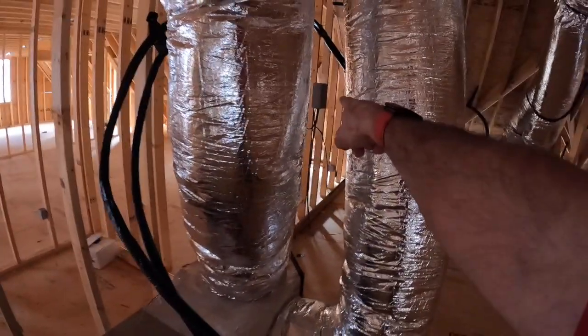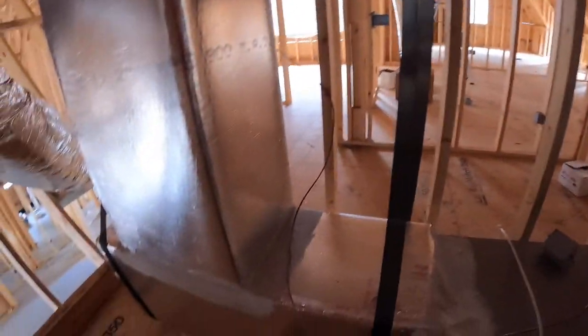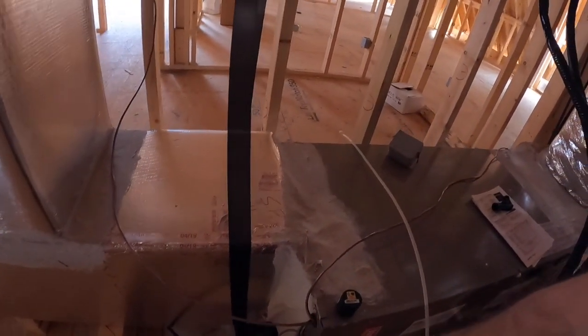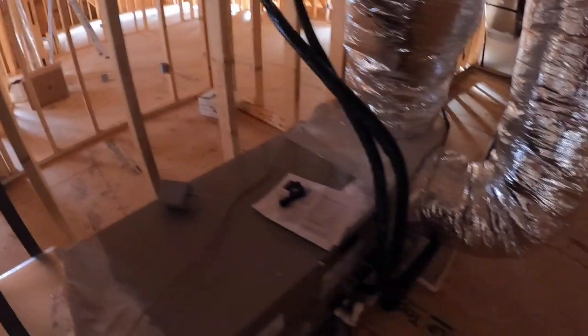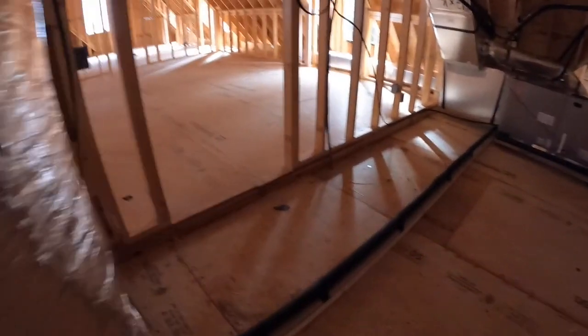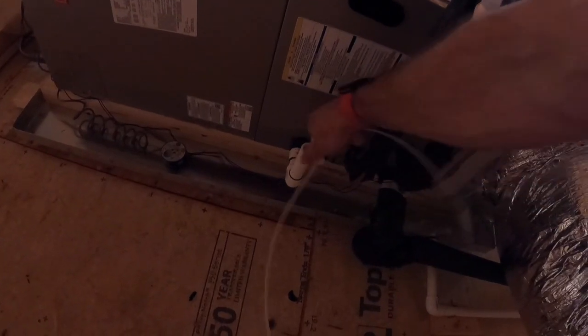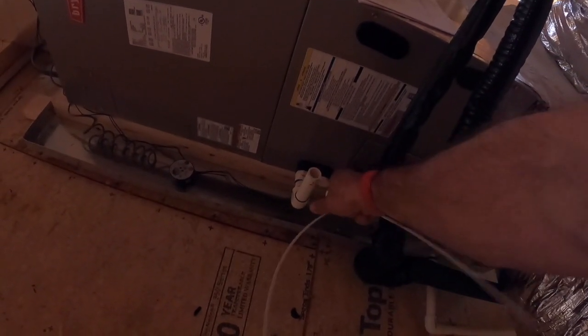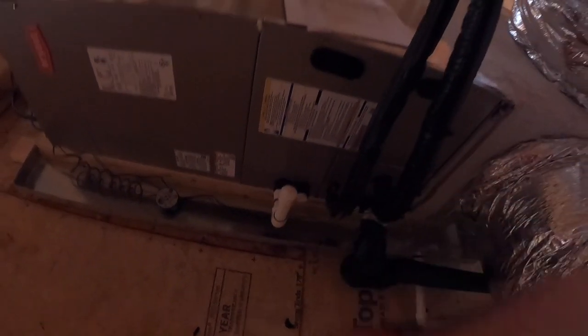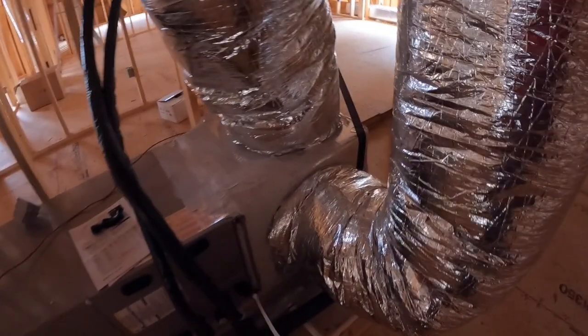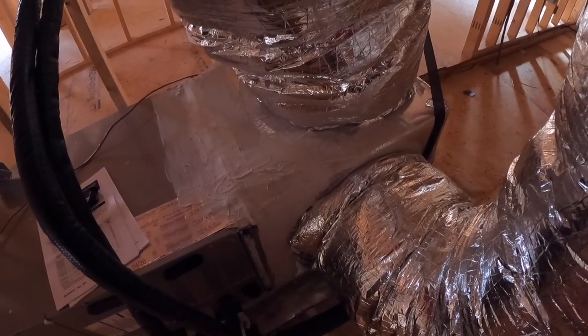And then we've got the same hookup here coming off of that same electrical panel over there. We've got the high voltage coming in on the bottom down here. The thermostat wires coming in here, surge protector. And then something else with the drain here. We put these in so we can take this cap off and pour our cleaning solution down through there to flush the drain pan out. And then if we just want to flush the drain line, we can take the top of the float switch out here and clean the line that way.